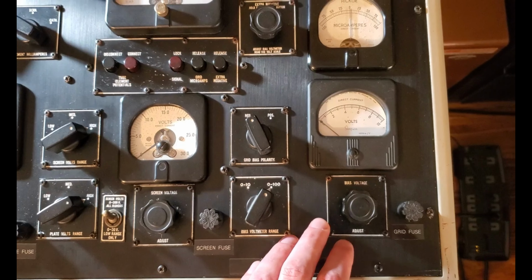So that's the bias section. Next, we get up to the grid control or grid signal section. So in series with the grid, we've got a microammeter that can read both positive or negative grid current. So we can check for things like ionization or cathode material that's gotten deposited onto the grid. And then here we have our grid voltage range.